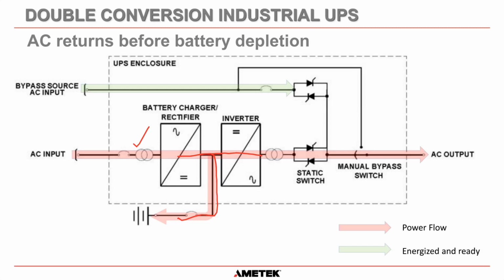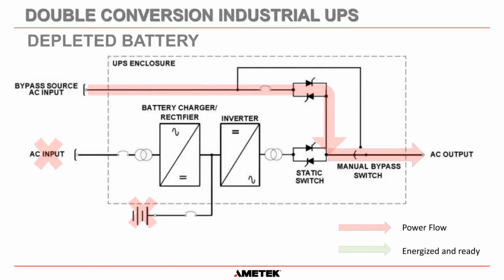You don't have to turn a switch on. You don't have to set something up to do this. This is done automatically within our system. As soon as it sees that the AC is good again, it goes back to normal operation. But let's say the AC was out for a prolonged period of time. So let's say the AC has been out for about 5 hours now, and depending on the size of your battery may be getting to the stage where it is depleted.